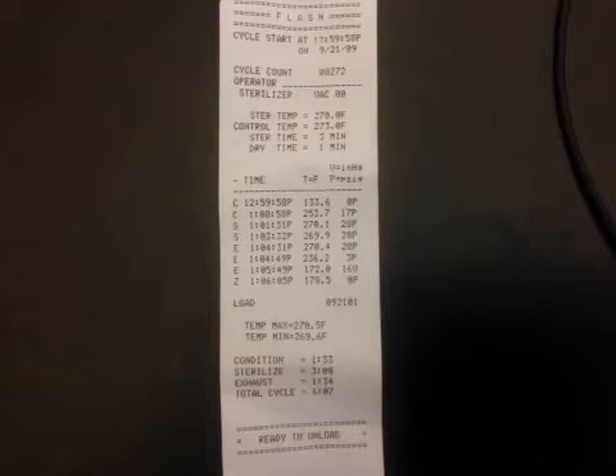In this recording, we're going to look at three different sterilizer readouts or cycle records. We're going to look at a 3-minute steam sterilization. This is for immediate use sterilizing, meaning open container. And then we'll look at a 10-minute open container or immediate use sterilization cycle. And then a prevac cycle, also for immediate use open container type of sterilization. First, let's look at the 3-minute steam readout or record.